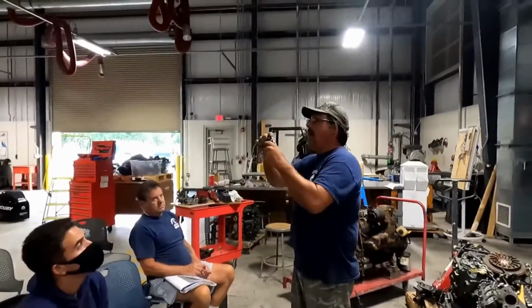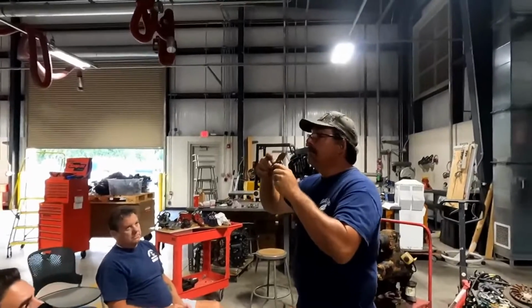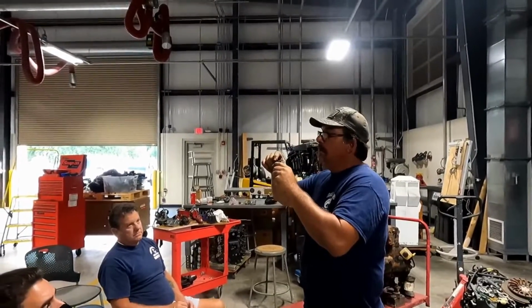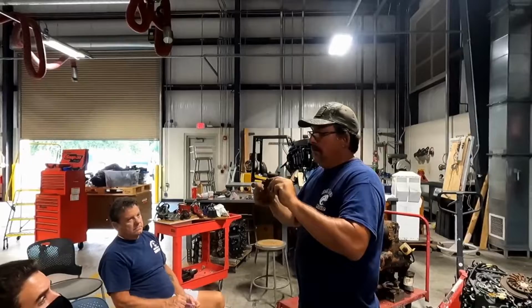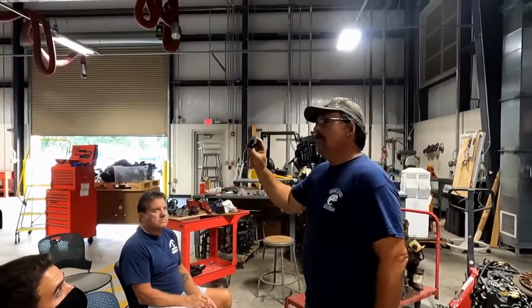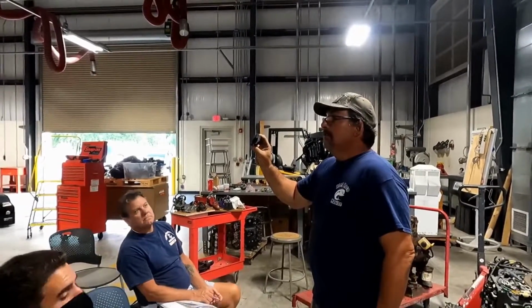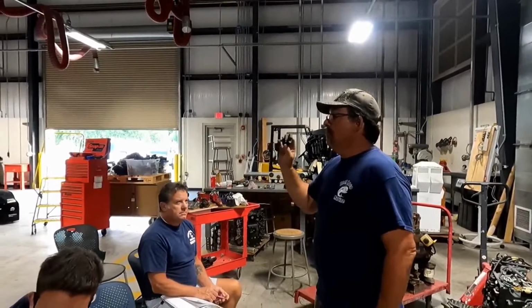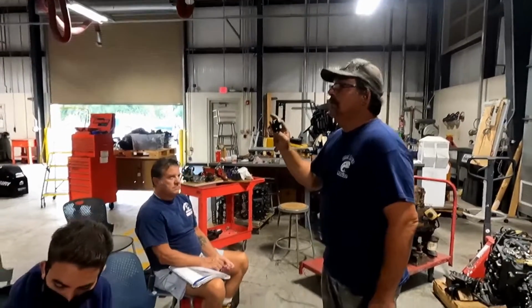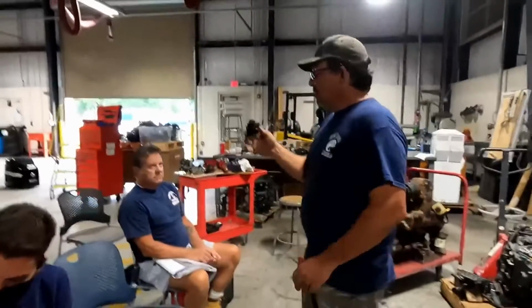Coils have little grounding, this one and most of them do. They have these groundings, okay? Look how dirty that is. I've seen worse, this is not so bad. So you have to check your grounds, because your number one electrical problem on most things is going to be a grounding issue. So you got to check the grounds.